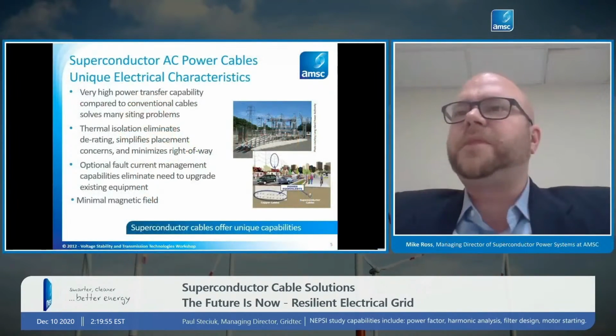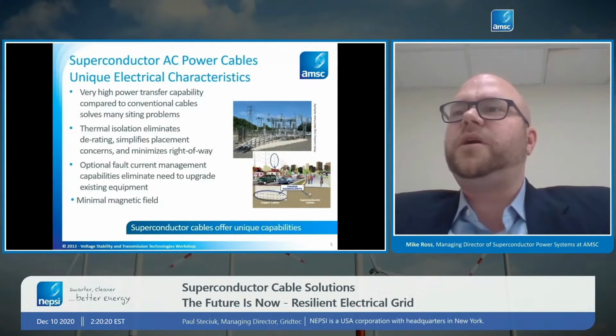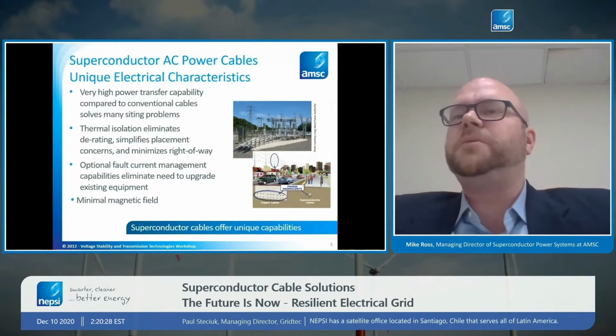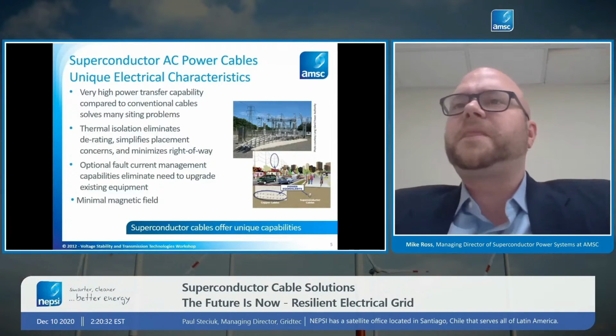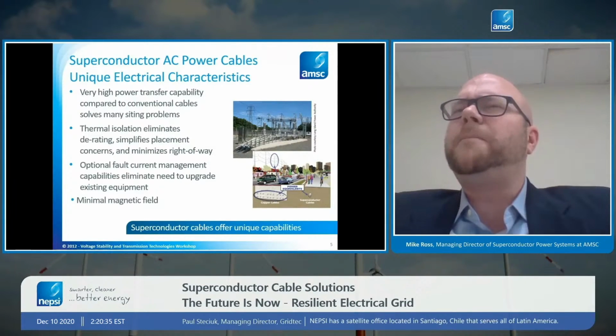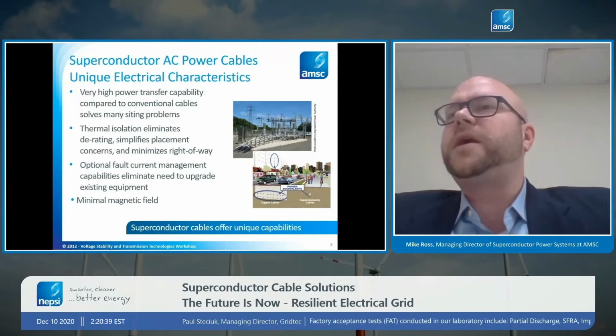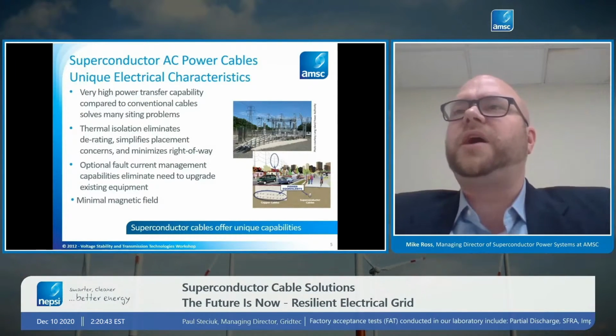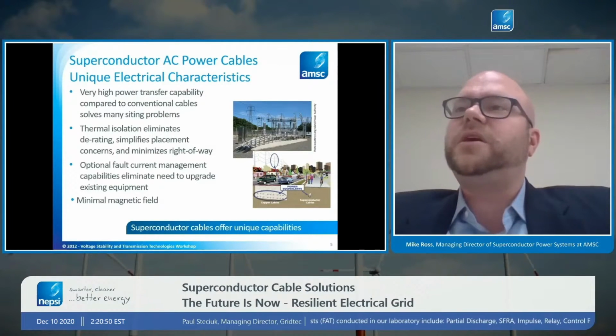With this technology, it limits the fault current, and then when the fault goes away, it goes back to being superconducting with no interaction between the operators or people in the field. It just naturally has that characteristic as part of the physics of the technology. So when we take this material and make power cables, those cables, as a result of using superconductor wire, have some interesting characteristics. The first thing is that there's very high power transfer capability. A typical power cable, the largest that you can buy, can handle about 1,000 amps. It's very difficult to find a power cable for utility applications that can handle more than 1,000 amps once it's installed and operating. Our cables can handle about 4,000 amps in their maximum design.